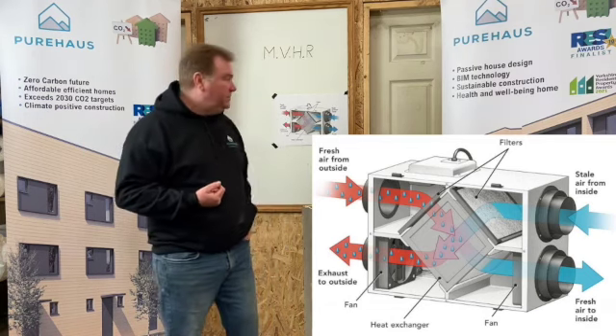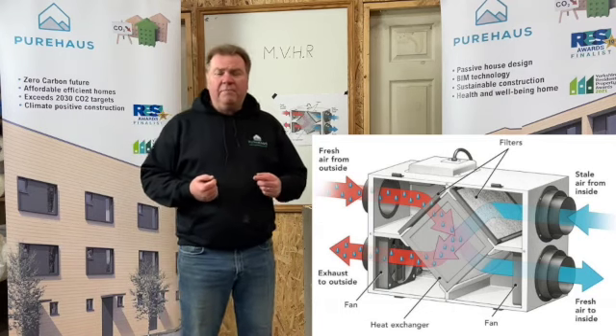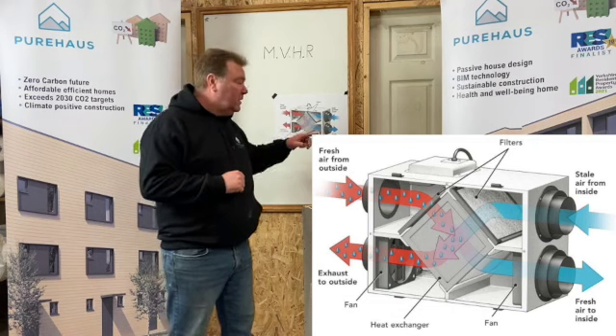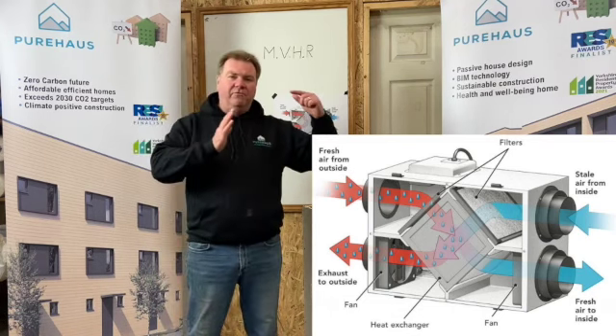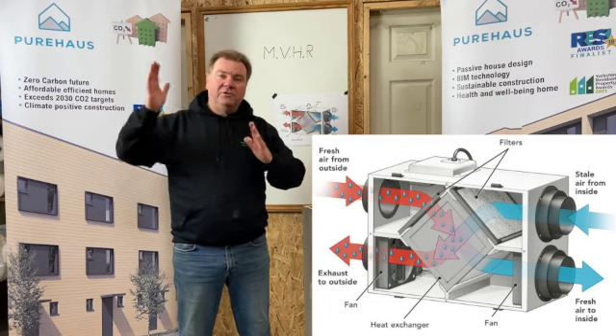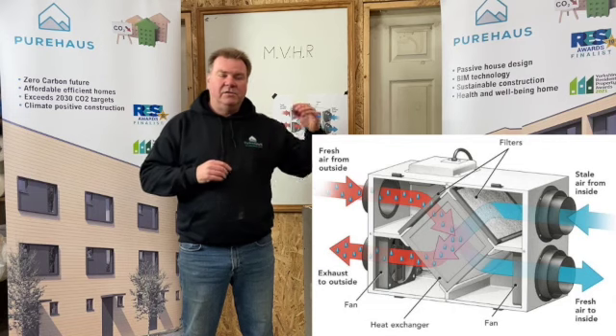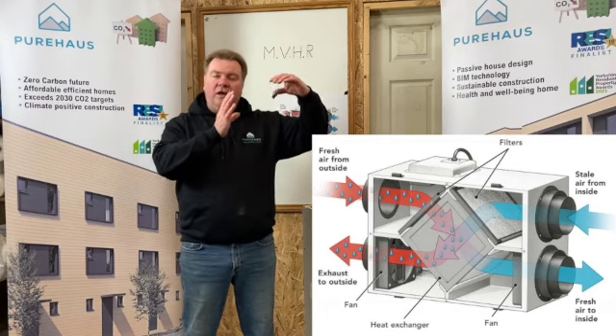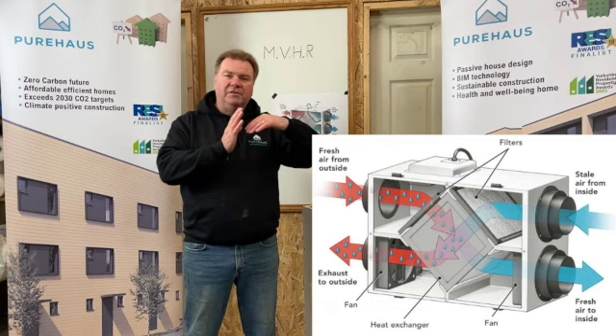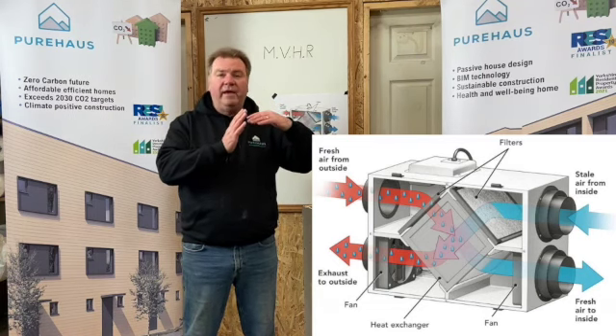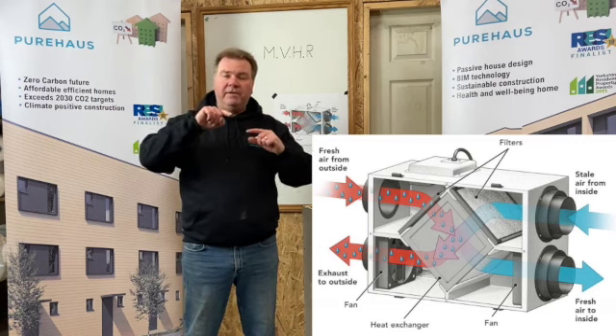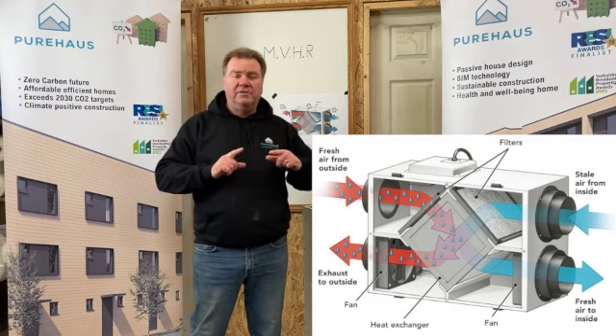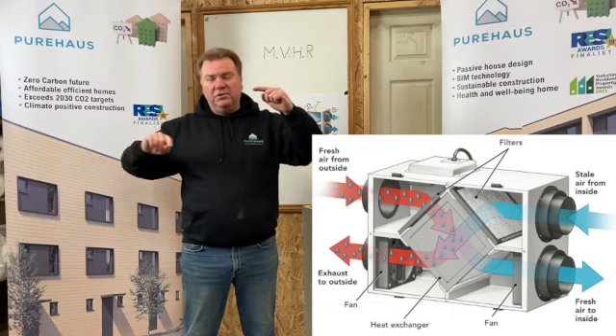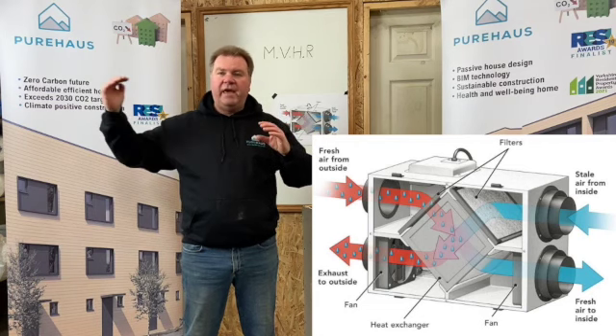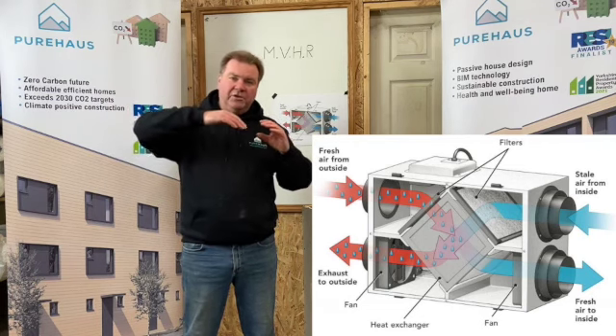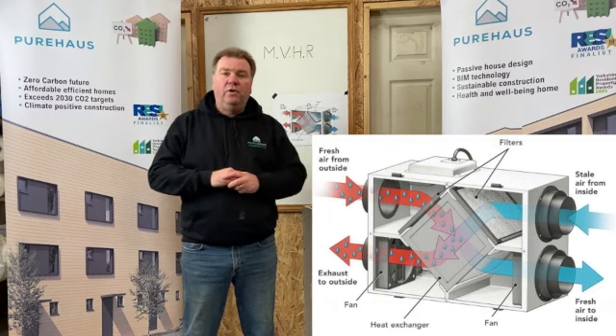Basically, it's an insulated box. Within that box we have two motors. Those two motors are pulling air in from outside and pulling air from the inside out. So what that does is it brings air from the outside in, goes through a filter. It filters out pollen, impurities, anything we don't want in the air. And it goes through the most important piece, the center, the heat exchanger - we'll go through that in a second. Then that air passes through and goes into the building. The other motor brings air from the inside, across through the heat exchanger, and exhausts it to the outside of the house.